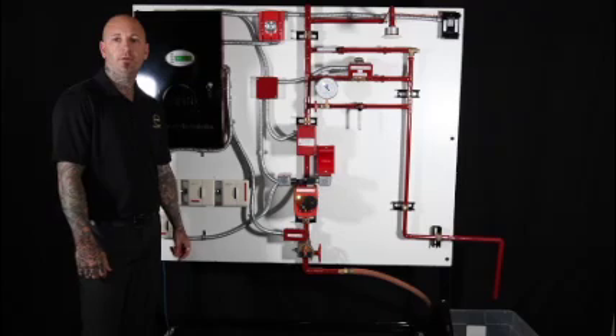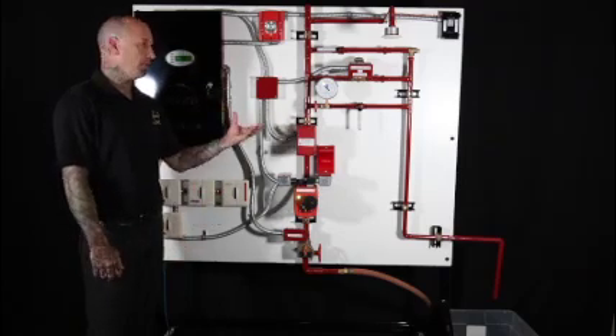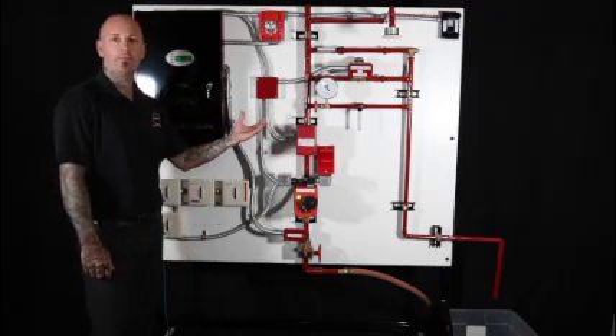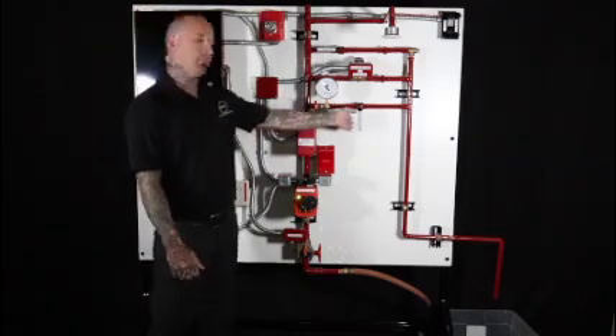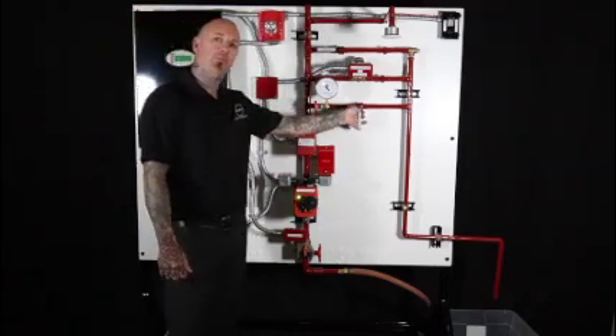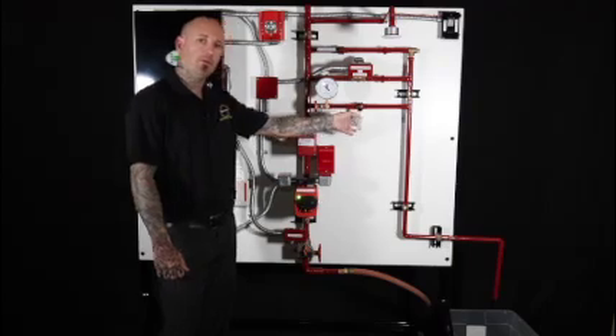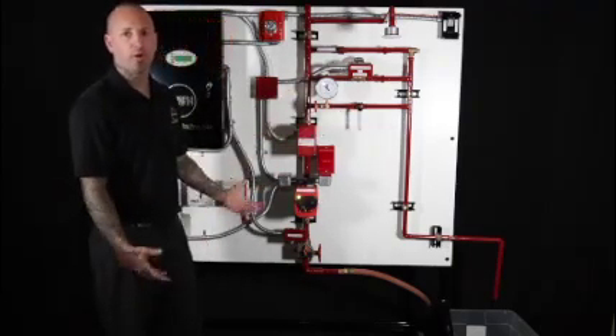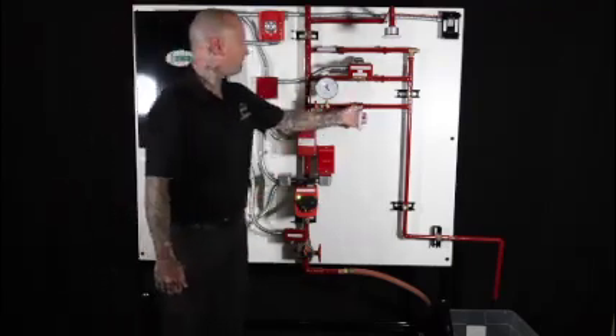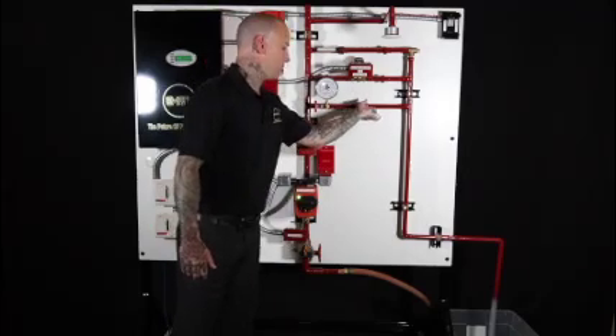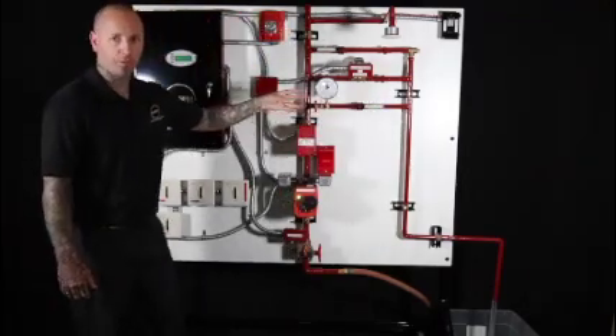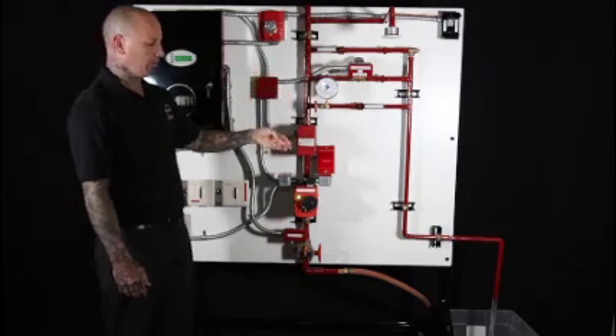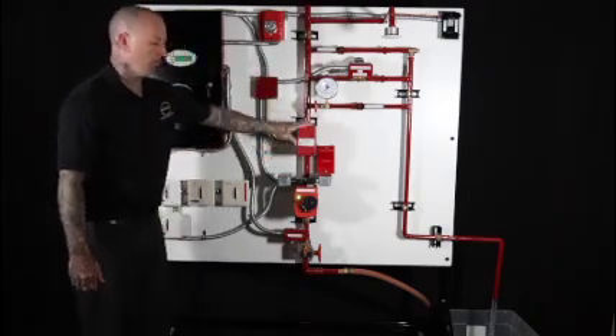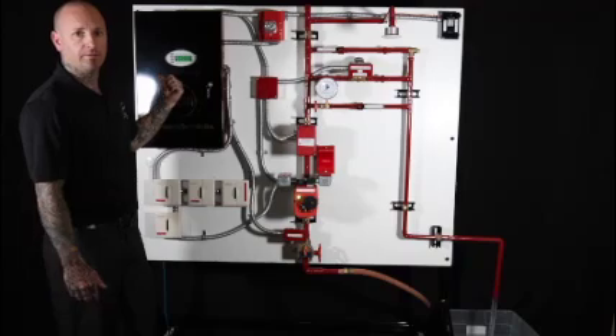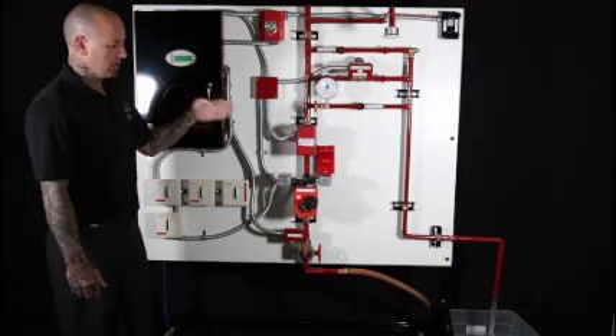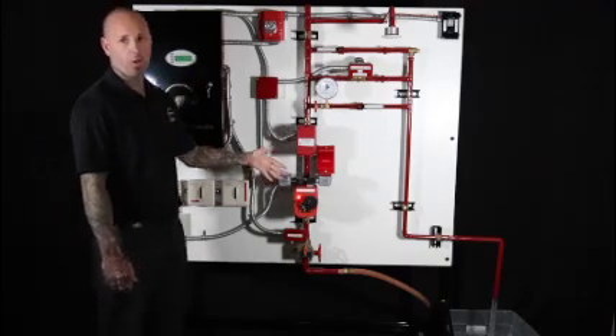Here in scenario 2, I'd like to show you a simulation of a broken sprinkler pipe. What I'm going to do is simulate a broken sprinkler pipe by opening the main drain to flow water. And then you'll watch the system work all on its own. So here we have a broken sprinkler pipe. Water starts flowing. The flow switch will detect it, send it to the alarm panel, and the system will shut down all on its own.